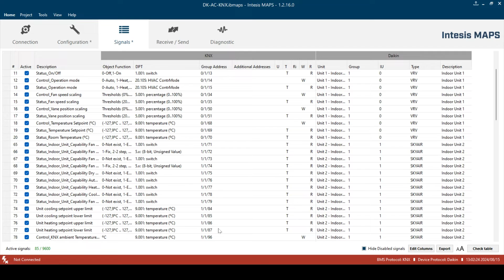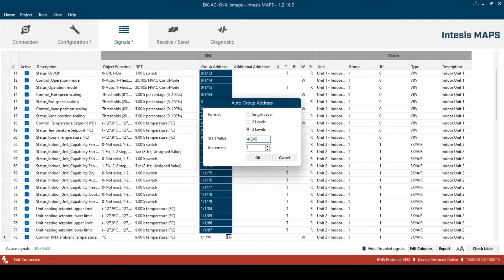If not, you can choose all your indoor unit addresses, go from 1 to the top, choose 3 level, and then choose where your air conditioner sits in the main, middle, and sub groups. So as a rough example, 4/0/0, increments of 1, and it'll automatically address all those.